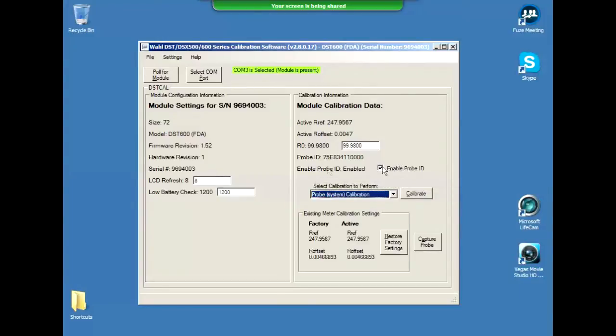If we're going to change the probe, and again, this is where I am not prepared, my apologies. I would disconnect the probe, connect the new probe. When I did that, and providing this is enabled, my meter would say PRB on it, telling me I have the wrong probe enabled. I would come down and I'd hit this capture probe button. Once you do that, it'll go out, read the new probe, it'll tell you what it is, it'll ask you, do you want to associate the meter with the new probe, this number, and your answers are yes or no. If you say yes, that will now allow that meter to take data from that probe, and only that probe. A meter can only be associated with one probe. And then your display, instead of displaying PRB, will go back to the current reading.